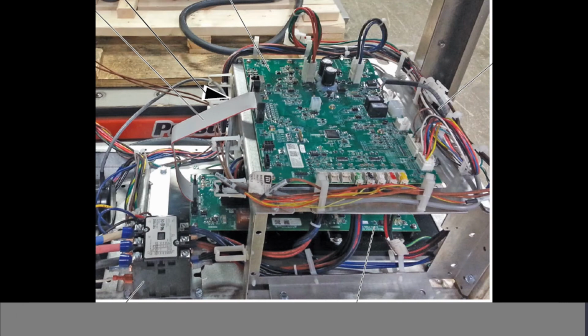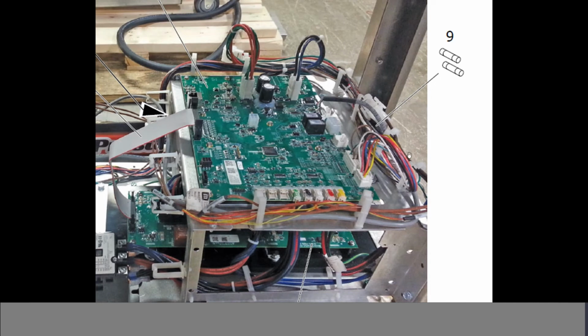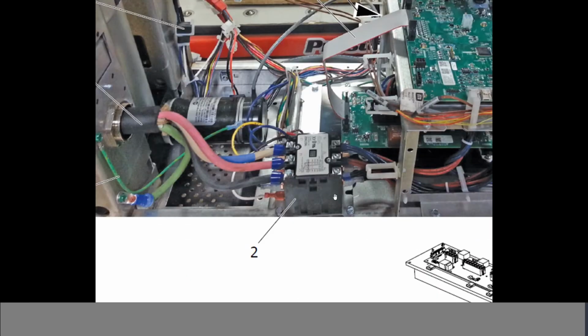Here's your SIB board, same SIB board. Here's your solid state relay board, same solid state relay board. What's different, we do not have a control contactor. We only have one contactor in this grill for Chick-fil-A. We don't have that control terminal block, so we don't have the fuses in the terminal block. We have the 10 amp fuses right here in inline fuses. Your contactor is a 208 240 volt contactor. Chick-fil-A does not use hood interlock systems. And you can see here the cord and plug set come directly into the contactor. So keep that in mind.